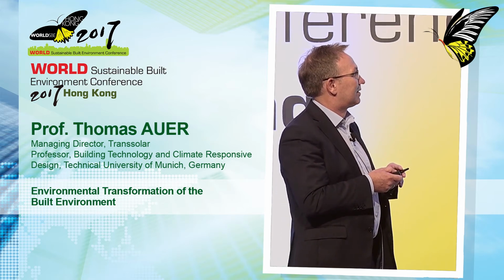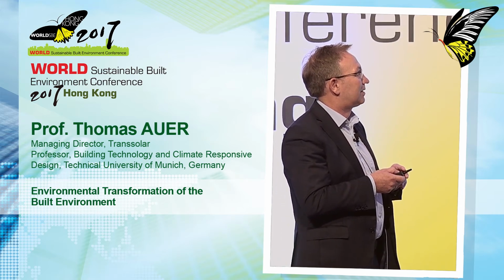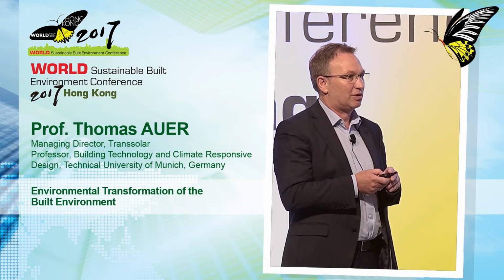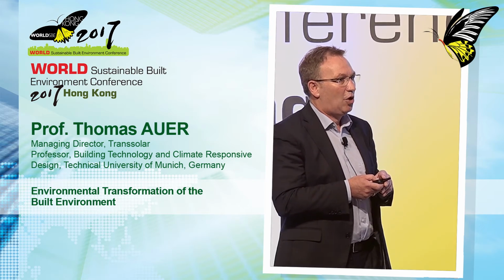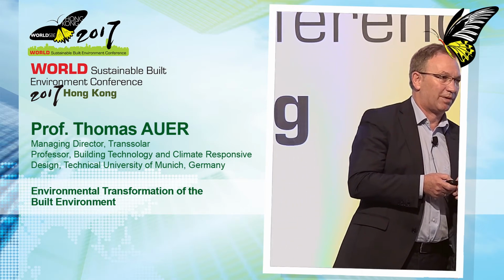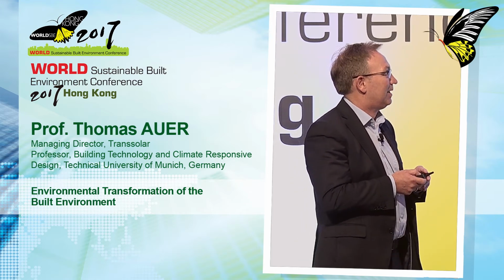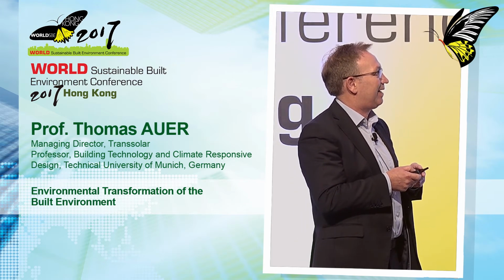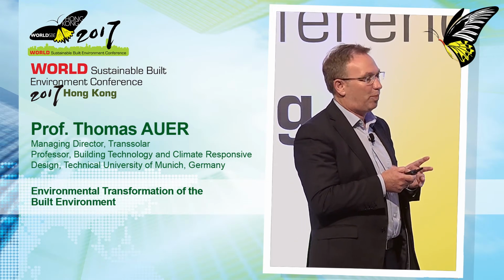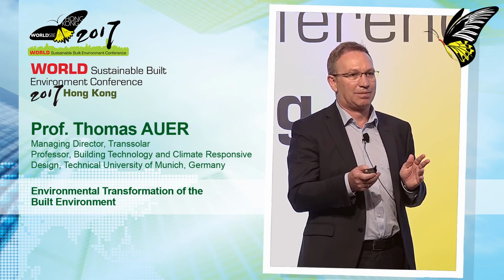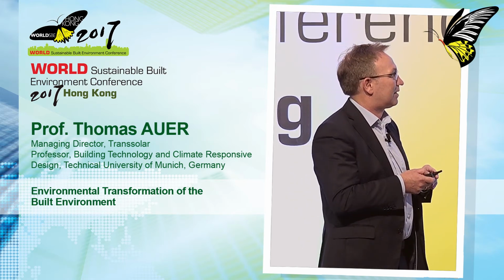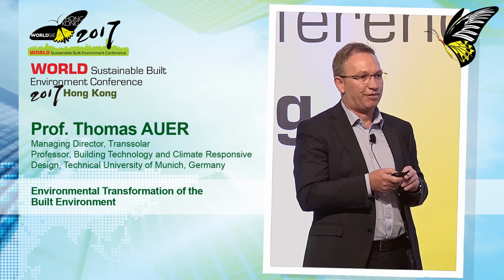You see that the comfort conditions we proposed, at 29 degrees air temperature and 29 degrees radiant temperature, would not provide a comfortable environment, so people would not be happy. But as soon as we add elevated airspeed at only 0.7 meters per second, which is not much, we get nicely into the comfort zone.